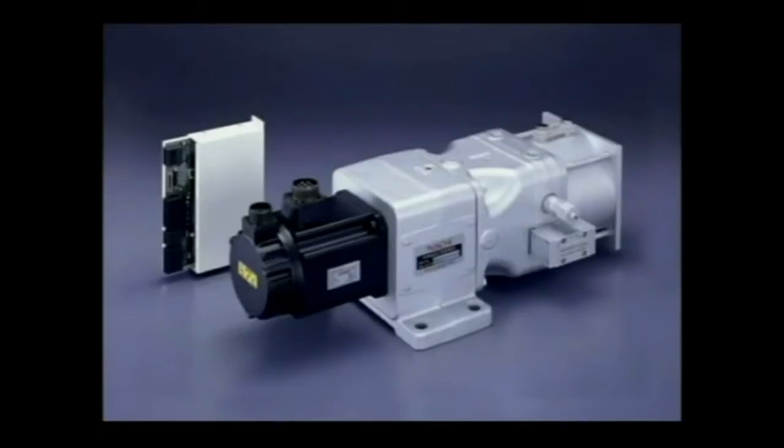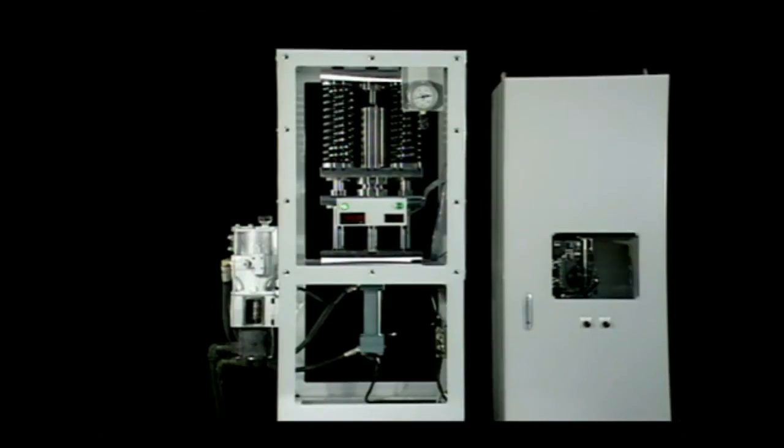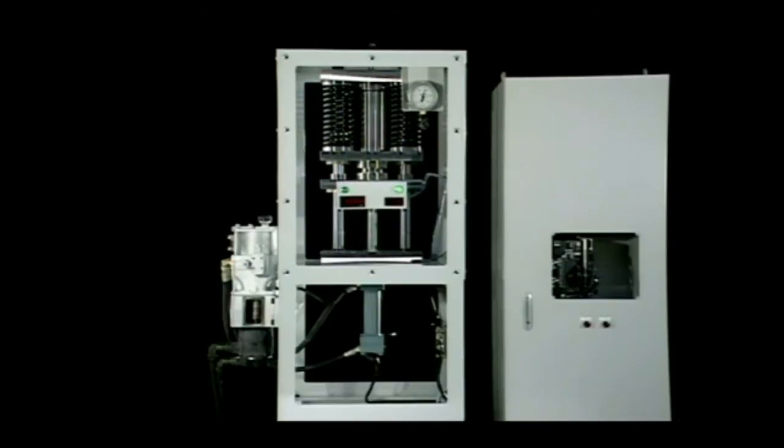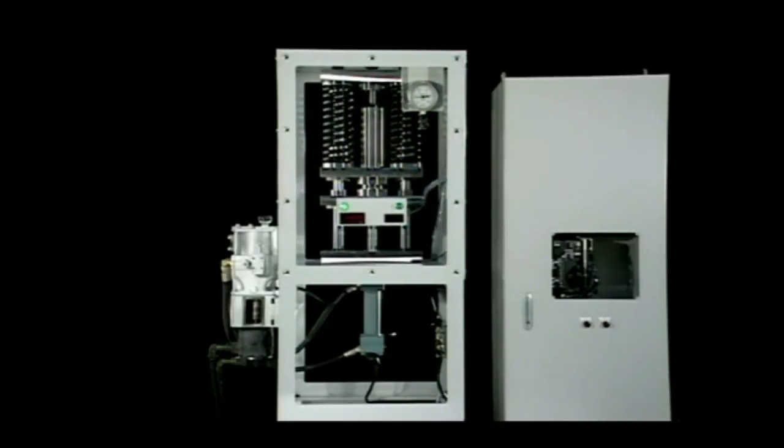The PowerMeister is a system for accurately controlling hydraulic cylinder thrust, speed, and position by operating a hydraulic pump with an AC servo motor to control the number of rotations and direction using digital control technology.